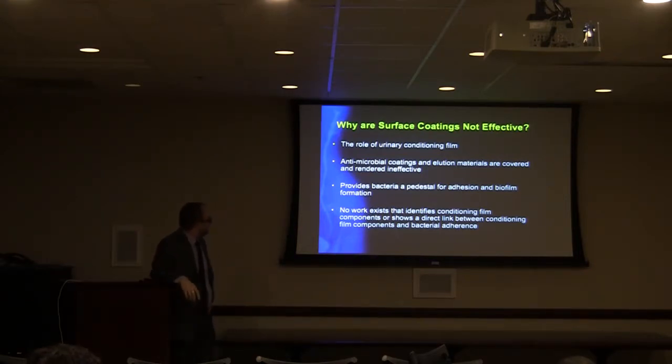Well, what does that do? It covers your novel antimicrobial coating or drug-eluting technology and basically renders it ineffective. The other hypothesis that was out there is that while doing that, it probably provided bacteria a pedestal for adhesion and biofilm formation, because bacteria produce adhesins that recognize and bind quite readily to a lot of these components that are found in urine. A lot of them are proteins.